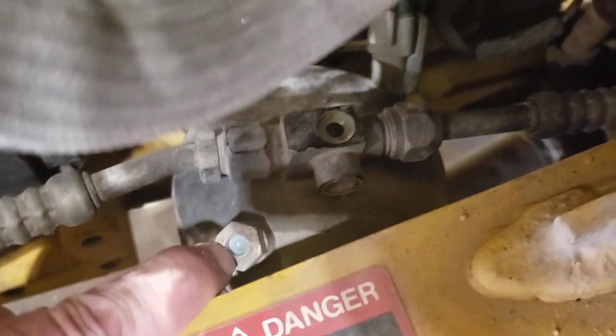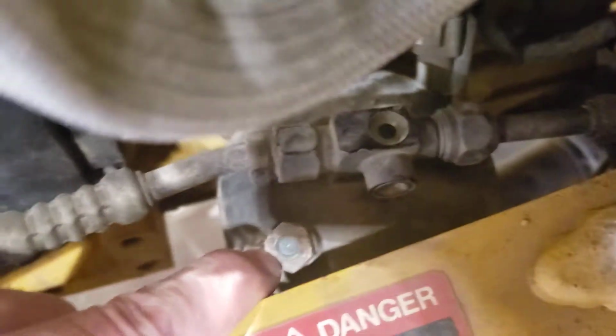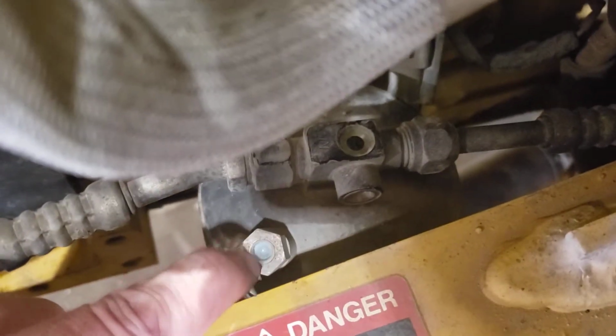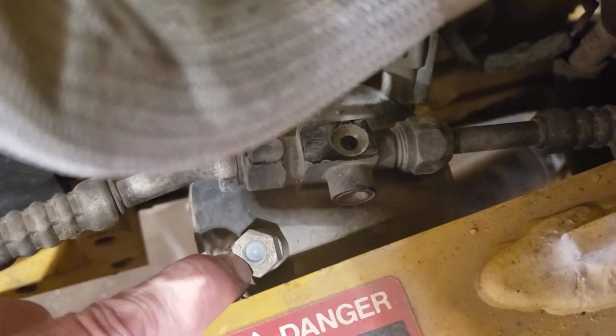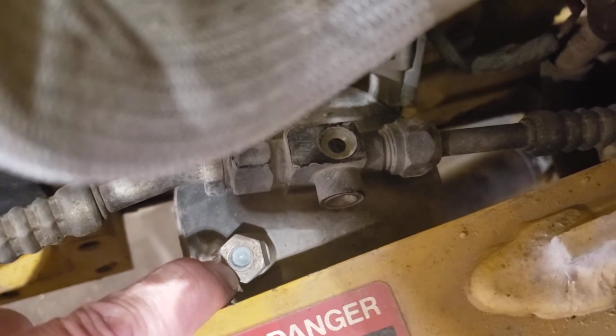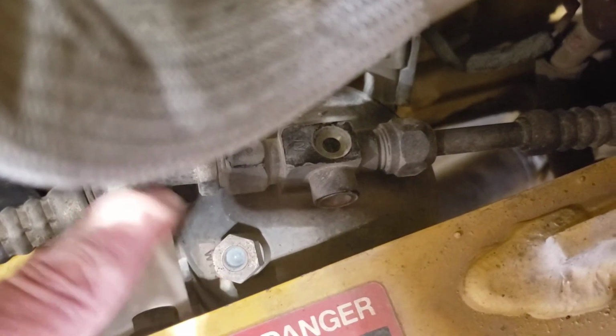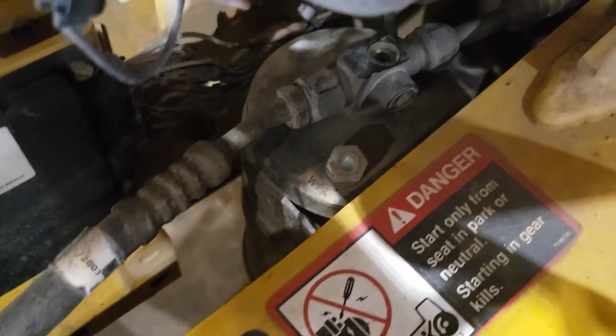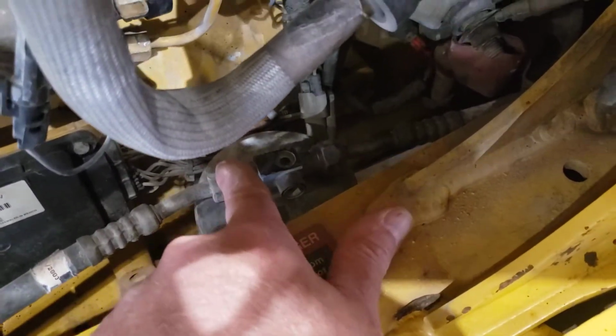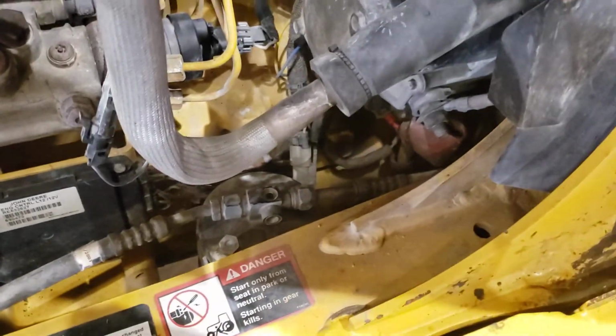And this one's also got a desiccant color window as well. If the desiccant has reacted with moisture, this is going to change color and tell you to change the receiver dryer, because the desiccant's no good in it anymore. So high pressure liquid coming into the receiver dryer, high pressure liquid leaving the receiver dryer, heading for the cab for the expansion valve.